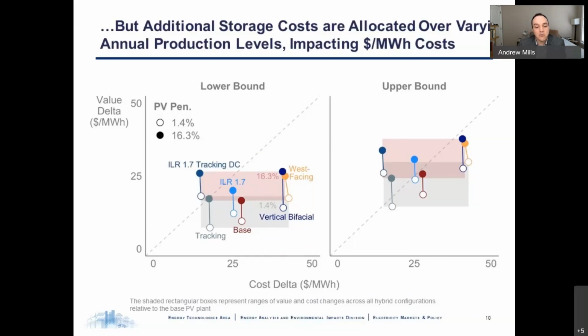What ends up happening is that the most attractive hybrids are those that maximize the energy production and end up with the smallest increase in costs relative to that base PV plant. In fact, the one that jumps out the most is a hybrid plant that combines the tracking with high inverter loading ratio and is DC coupled to capture that clipped energy.